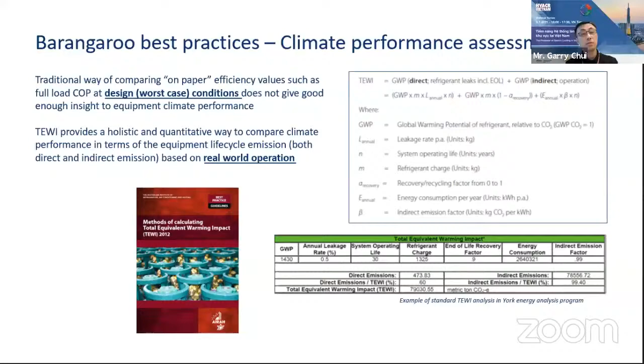So I took this case and did a TEWI analysis, just to show everyone the climate performance between the left-hand side, which is the traditional way of using constant speed centrifugal chillers for this district cooling with freshwater cooling towers in a parallel arrangement, and the right-hand side, which is based on the Barangaroo configuration, using variable speed centrifugal chillers, seawater cooling for heat rejection, and the series counterflow arrangement on the chiller plant. And you will see from the two TEWI tables at the bottom, on the left-hand side, can you click on the slides, please?